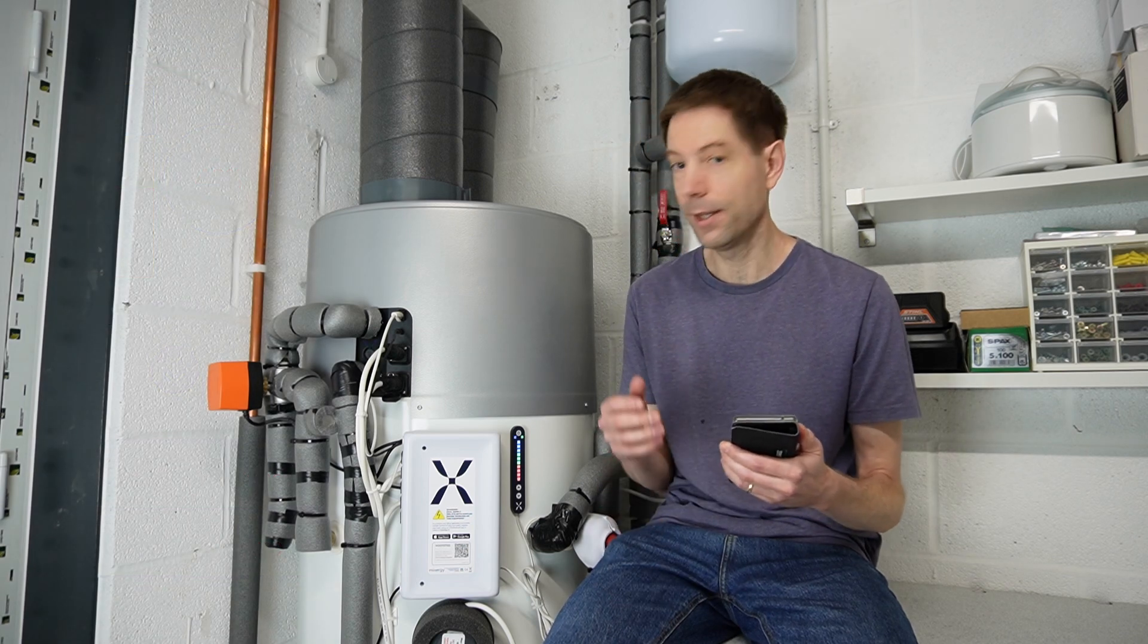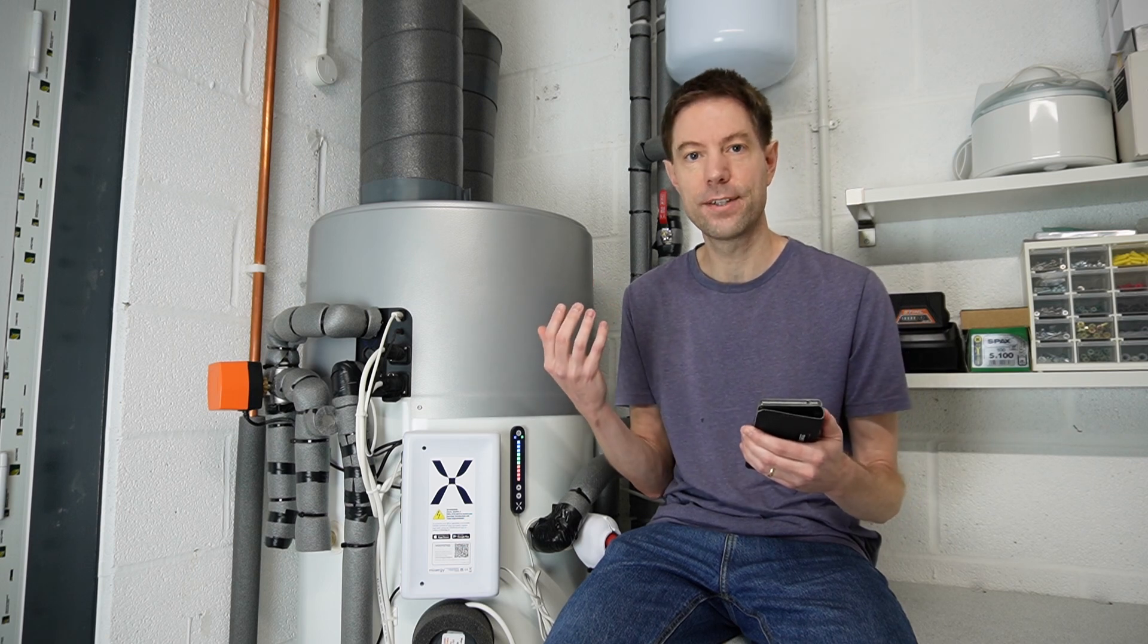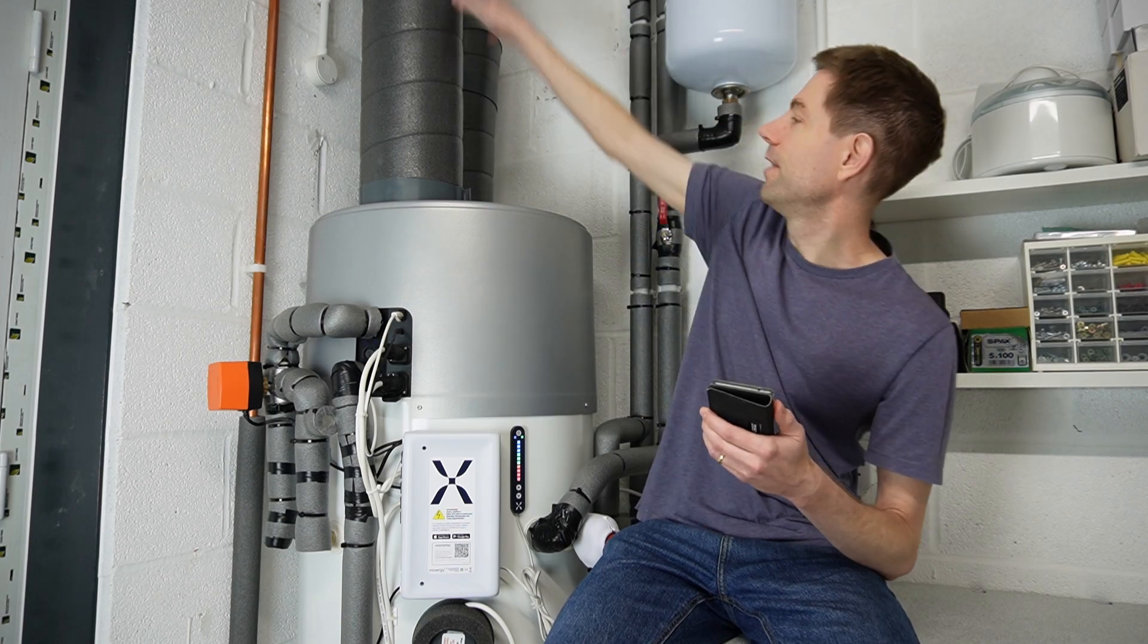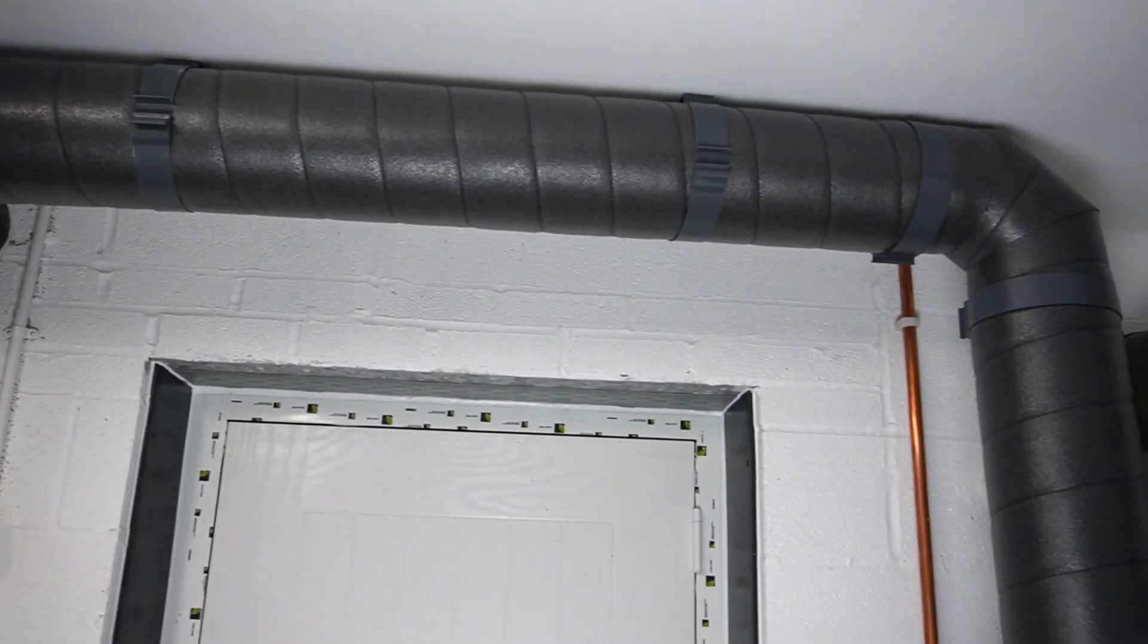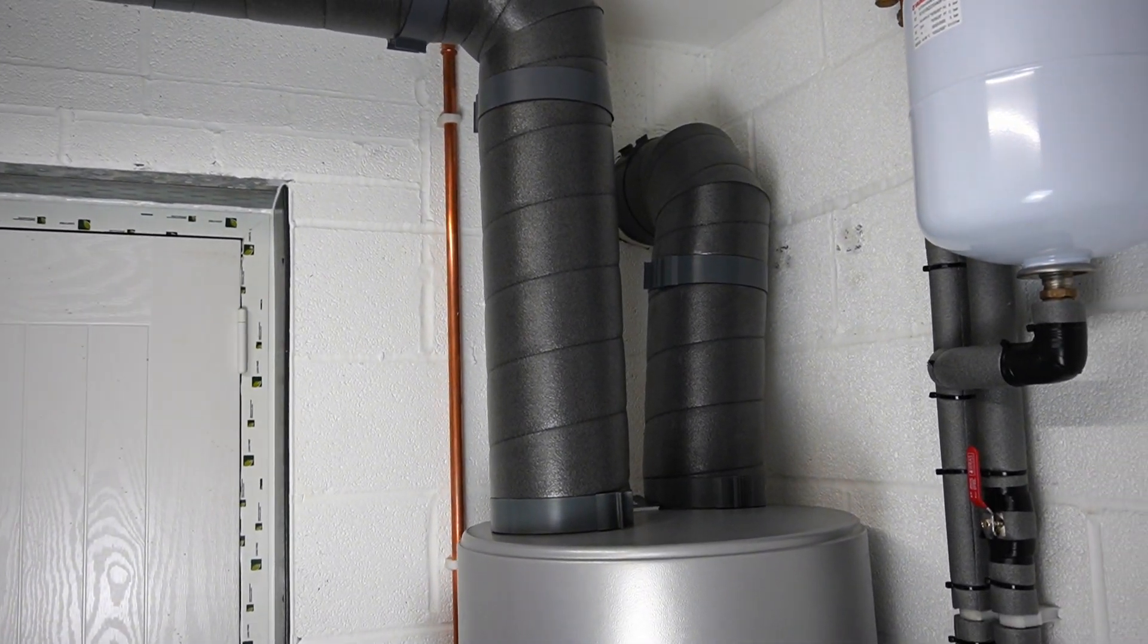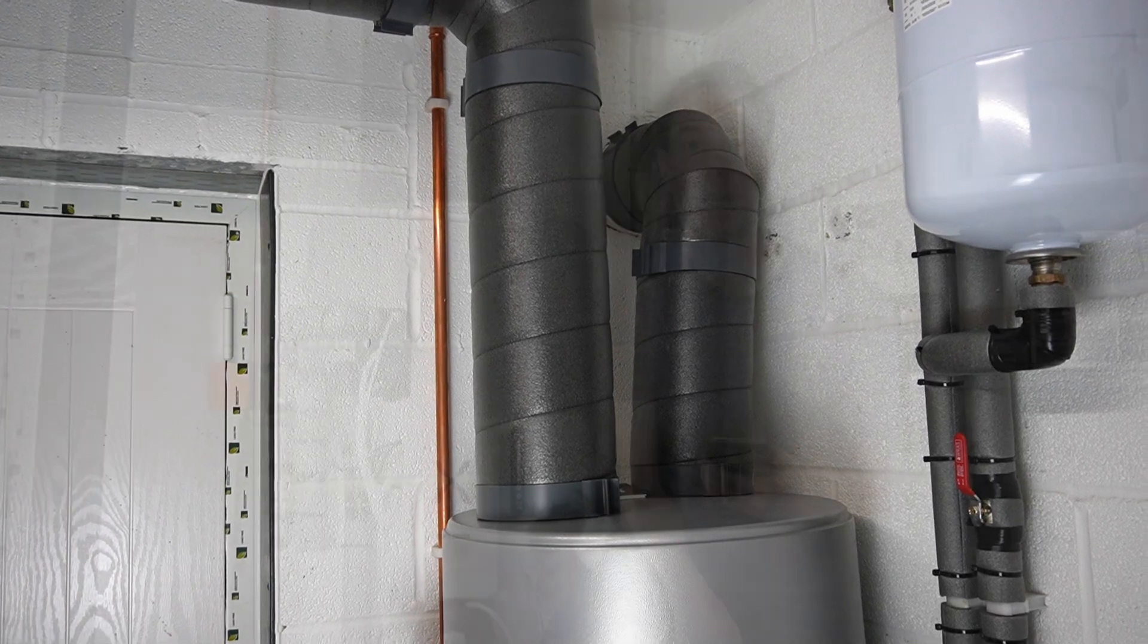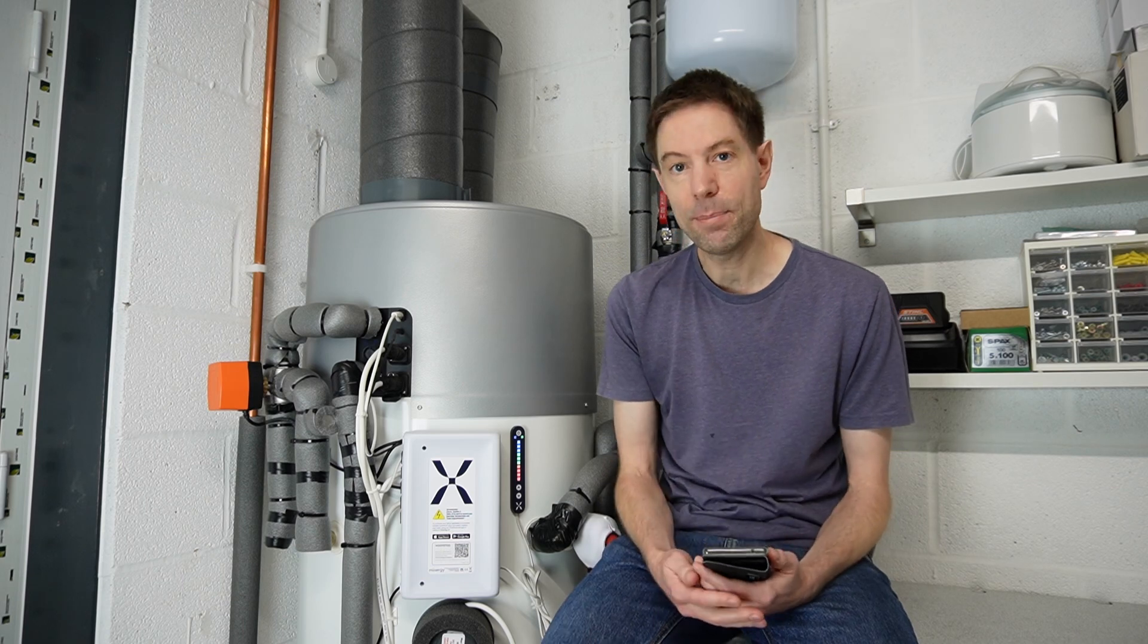And what happens then is that it will start to draw air in through the vents that are installed up here, pull air into this one here, it'll do the heat exchanging in the heat pump and then the cold air gets spat out through this second vent. And I'll take you outside in a minute as well to show you how loud the vents are as well. So it's now kicked in, this is now running and roughly I'd say this is about as loud as it ever gets.